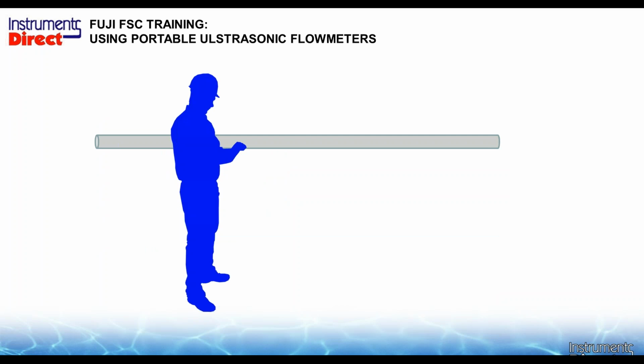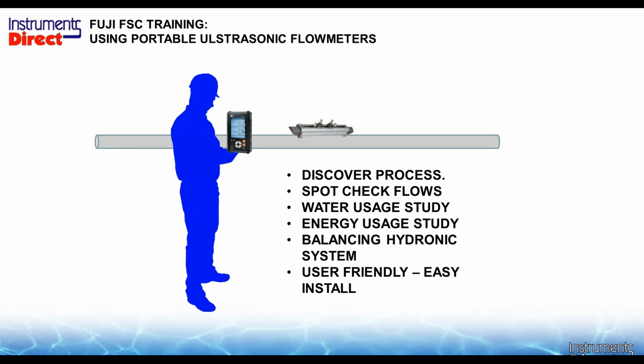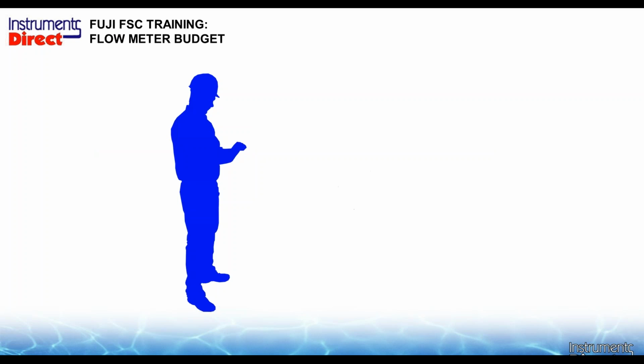So in using this device, the benefits again are, one, we clamp it on the outside of the pipe. And the main purpose of having this on a portable device is that going through a spot check or a discovery process. I want to put a new chiller in my facility. What's my flow? Not really sure. Okay, you're going to go through the discovery process to find out what the capacities are, what the flow rates are, and in some cases what the energy is. So a nice device, simple to use, clamp it on the outside of the pipe, no holes inside the pipe, and to harvest your data or to store your data. And on top of that, as we said, it's very user-friendly to use.